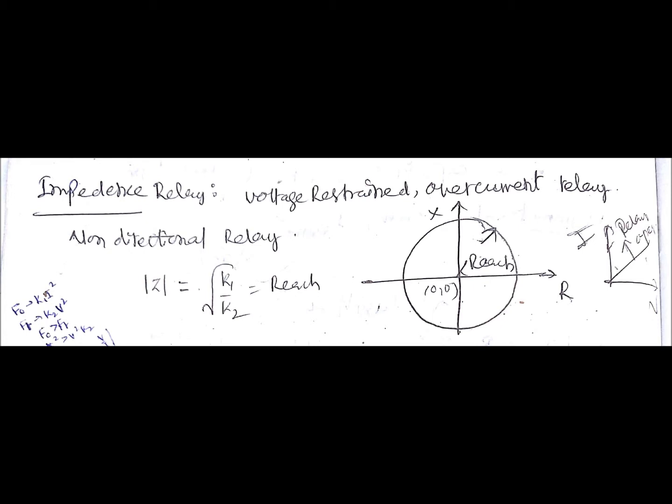Coming to the impedance relay — it is a voltage-restrained overcurrent relay. The restraining force is due to voltage in the case of the impedance relay. We need both operating force and restraining force for a relay to operate. The restraining force is due to voltage and the operating force is due to current, since it operates only when current becomes greater than the pickup value.